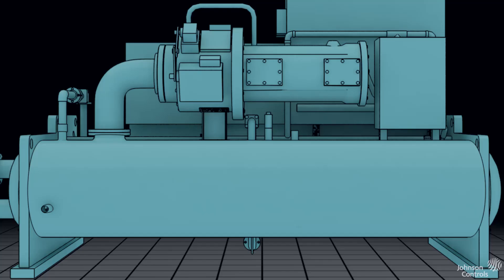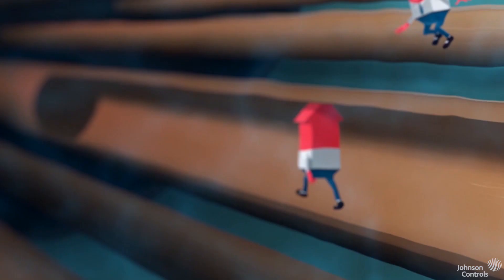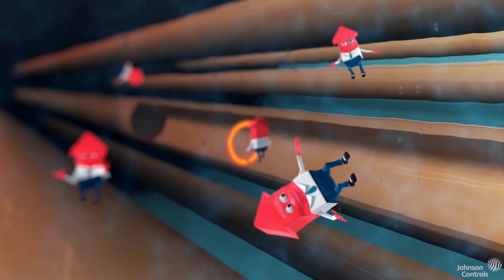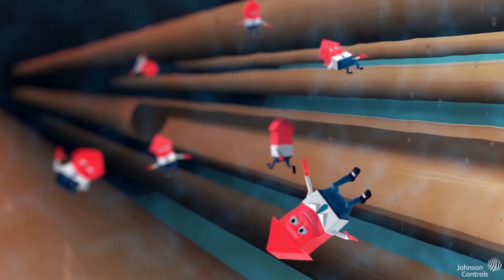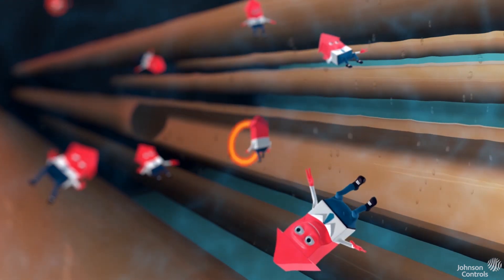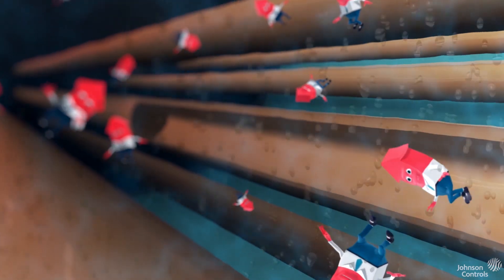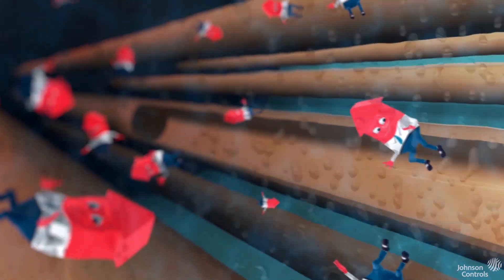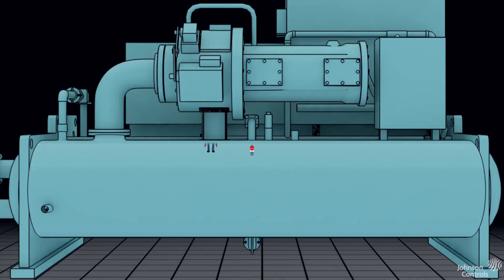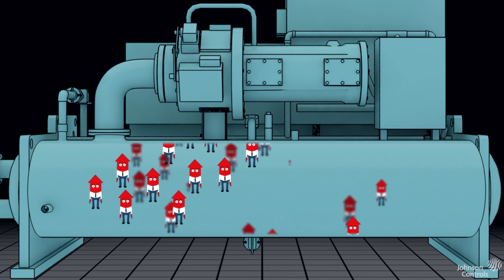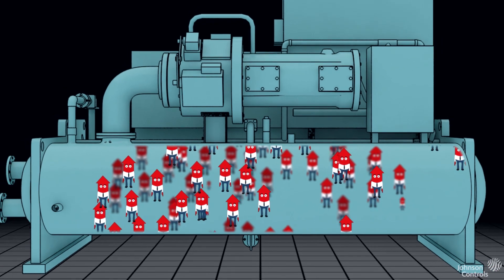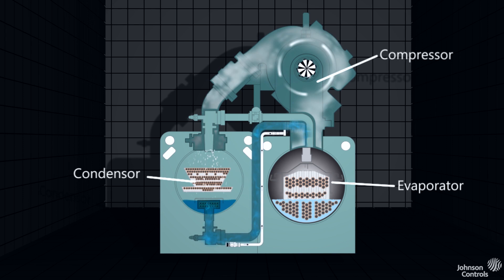As the chilled water returns to the chiller, it passes through narrow tubes that are submerged in a liquid chemical refrigerant. By design, any heat added here will cause this refrigerant to boil, changing state from a liquid into a gas. Mr. BTU can't hang around here long though, as a chiller is not designed to store heat energy.